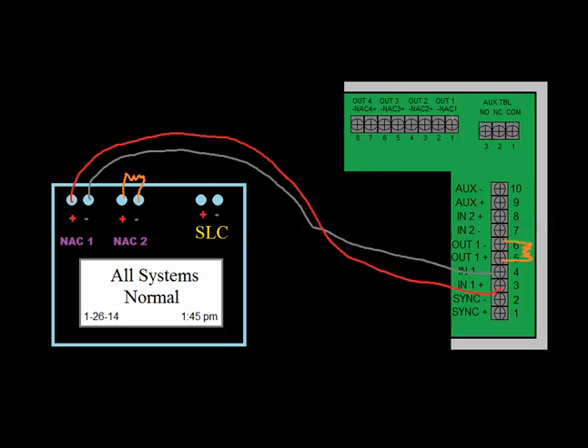If there's any trouble, let's say NAC 1 doesn't see a resistor. If we had the resistor, but then that opens up, it goes into trouble. Now these terminals 5 and 3 are going to open up, and what that's going to do is show up on this panel as an open circuit. It's going to say open circuit NAC 1. So it's a pretty common trouble. If I went to a service call and saw open circuit NAC 1, the first thing I'm going to ask myself is, is this NAC 1 tripping a power supply?